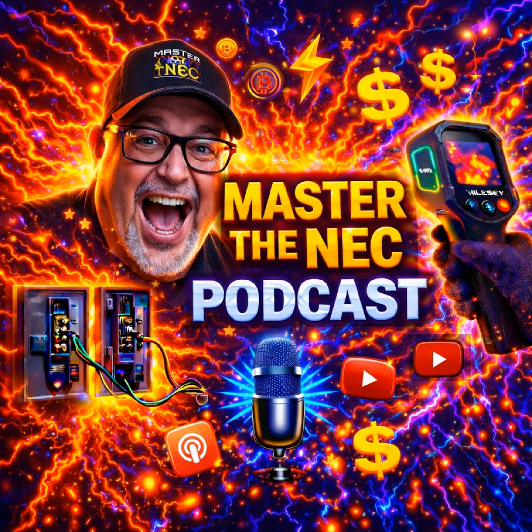I think somebody's going to hear that statement and say, wait a minute, Paul, what I'm interpreting from that statement is that a floating generator can't shock you. Absolutely not what we're saying. So don't make that leap. I hear this all the time. They say, well, Paul, if it's not bonded, then there's no way for current to get back. There's no way that you can get shocked. That is not true. Do not make that leap.